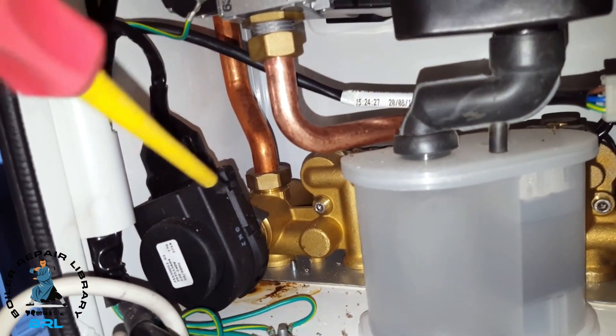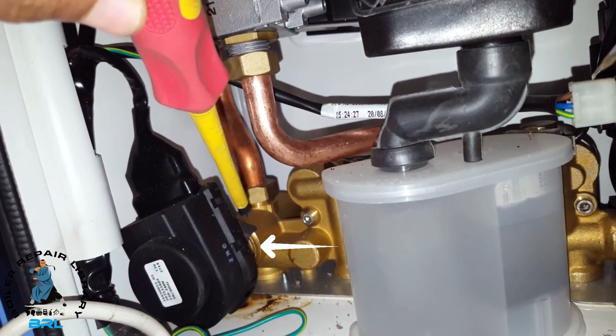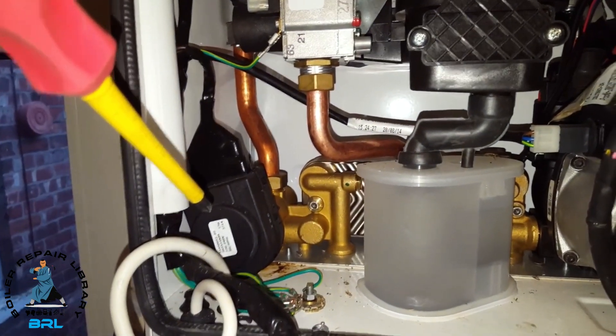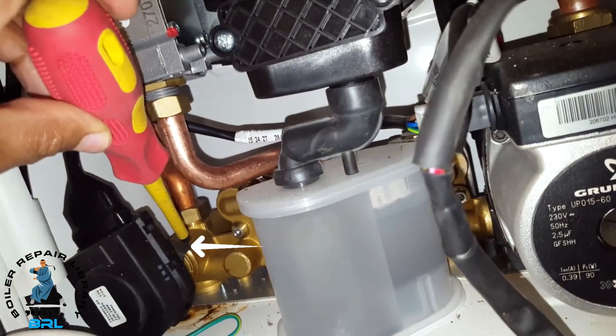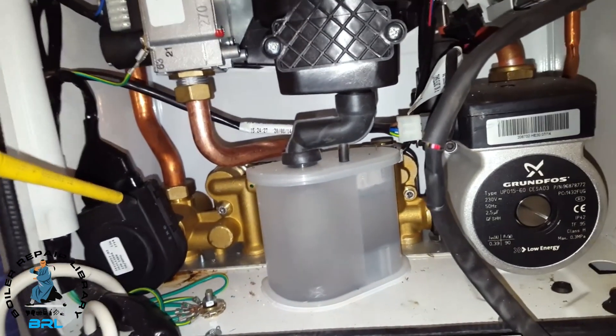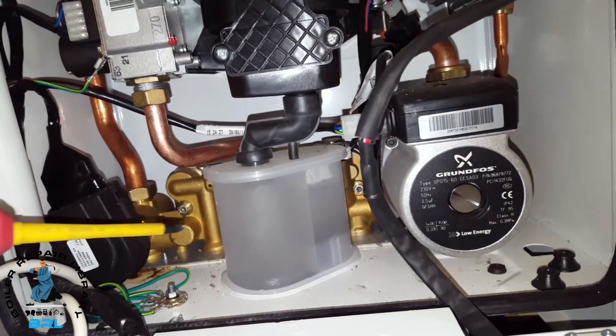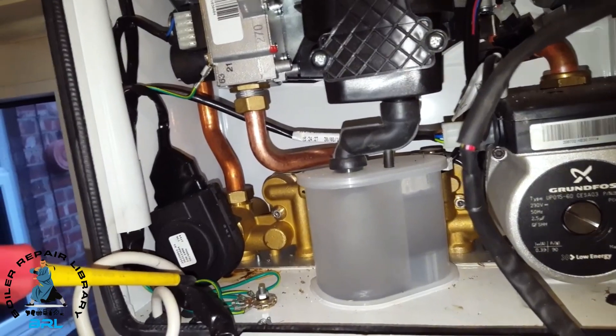What's happening is that when the diverter valve is moving in and out, it's leaking from the cartridge which is just behind the actuator. To fix this, you have to turn the boiler off and drain it all down. Remove the actuator with the clip — just pull that off. Once it's drained down, you also need to take out the condensate trap in order to access the cartridge, then screw it out and replace it.